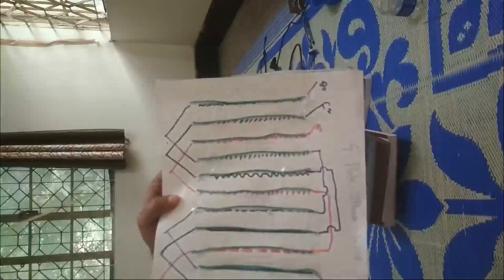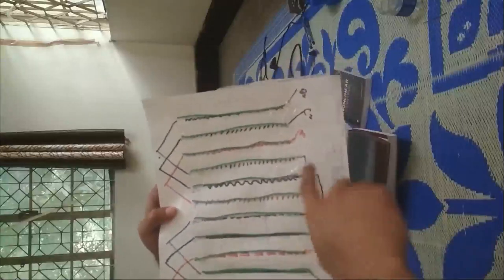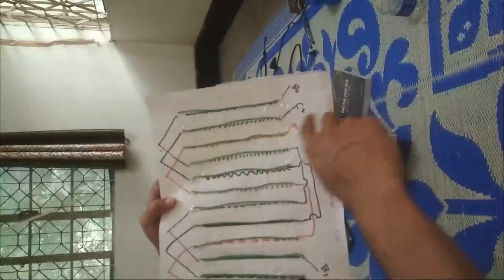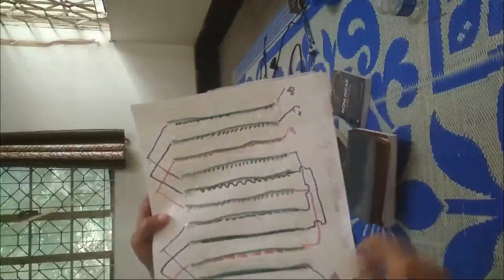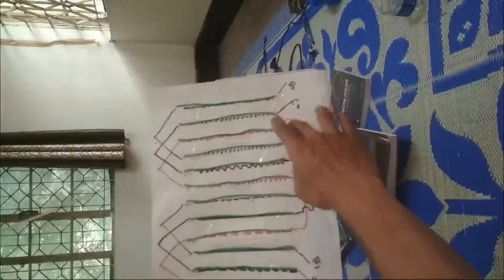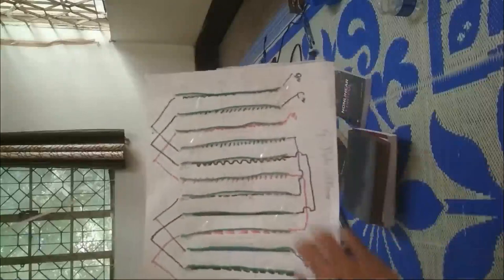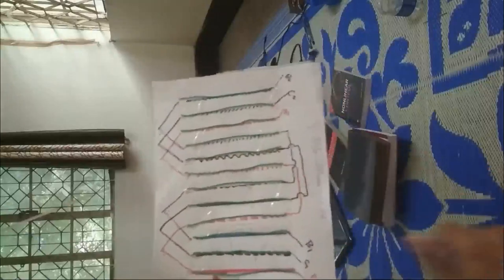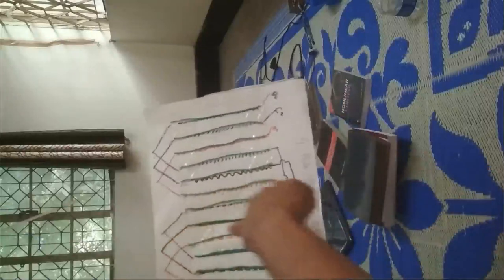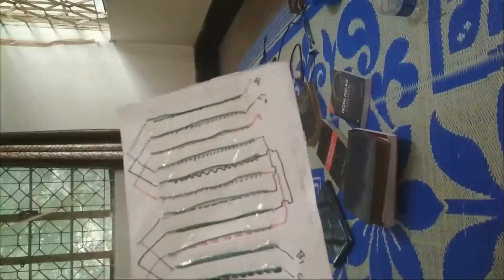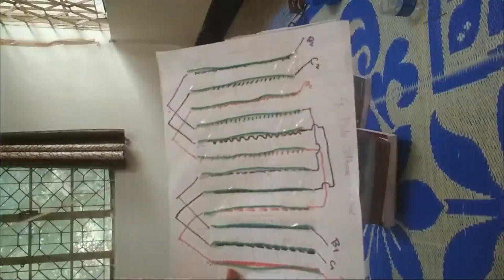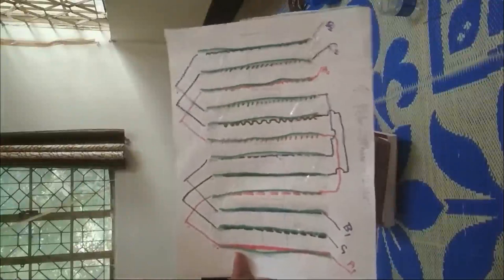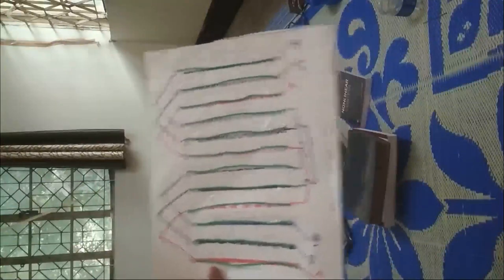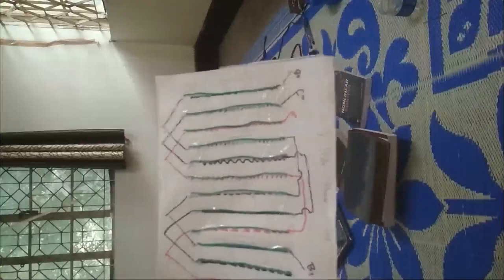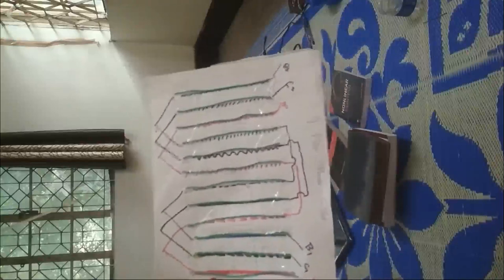So how do you connect A1, A2 in series, and then you are getting the terminal for A for wave connection. Similarly for B, you should connect them in series. Obviously, if you connect all the A in series, you have to connect all the B in series, and you have to connect all the C in series. You cannot connect A in parallel, B in series, then C in parallel. Then that will cause an imbalance in voltage.